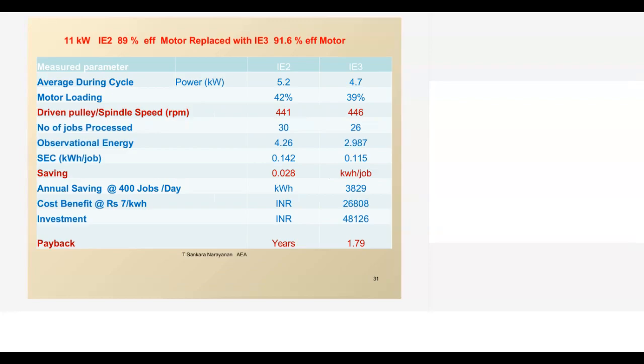So this is a case given for IE2 to IE3 motor. The existing 11 kilowatt IE2 motor has 89% design efficiency. This was replaced with an IE3 motor of 91.6%. This replacement was done in an engineering industry where automobile cylinder heads are drilled. It is a multi-drill machine, with more than 11 drills at a time, drilling the cylinder head.